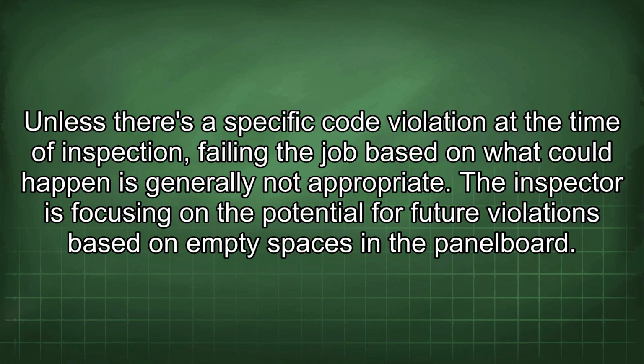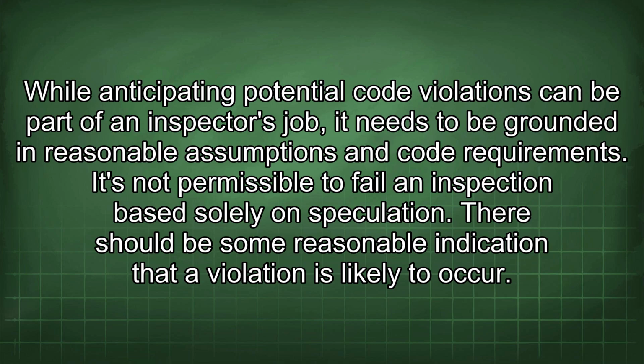The inspector is focusing on the potential for future violations based on empty spaces in the panel board. While anticipating potential code violations can be part of an inspector's job, it needs to be grounded in reasonable assumptions and code requirements. It's not permissible to fail an inspection based solely on speculation. There should be some reasonable indication that a violation is likely to occur.